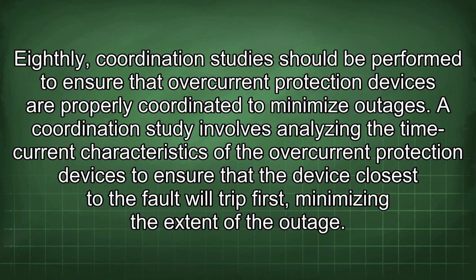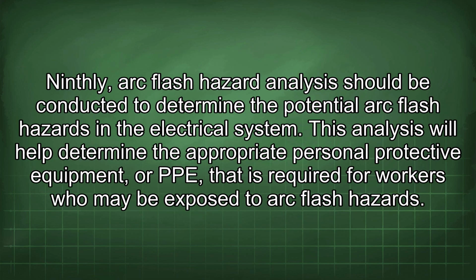Eighthly, coordination studies should be performed to ensure that overcurrent protection devices are properly coordinated to minimize outages. A coordination study involves analyzing the time current characteristics of the overcurrent protection devices to ensure that the device closest to the fault will trip first, minimizing the extent of the outage. Ninthly, arc flash hazard analysis should be conducted to determine the potential arc flash hazards in the electrical system. This analysis will help determine the appropriate personal protective equipment, or PPE, that is required for workers who may be exposed to arc flash hazards.